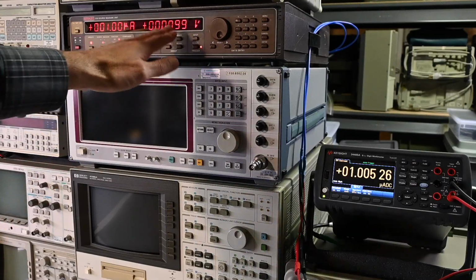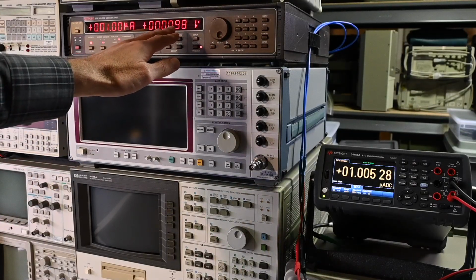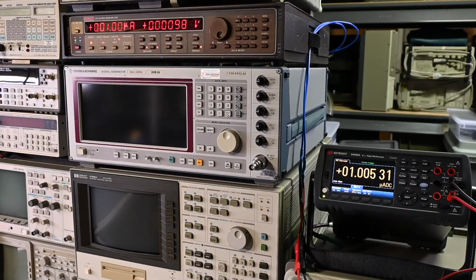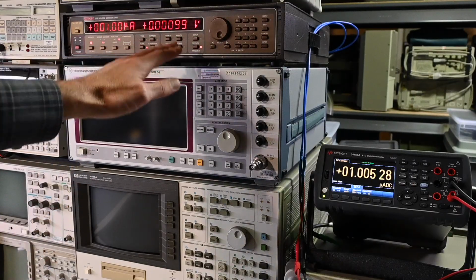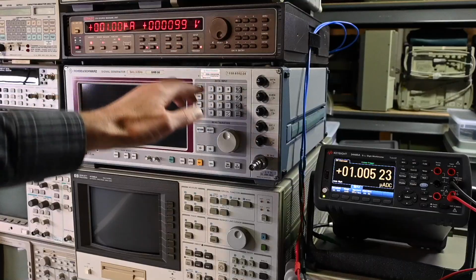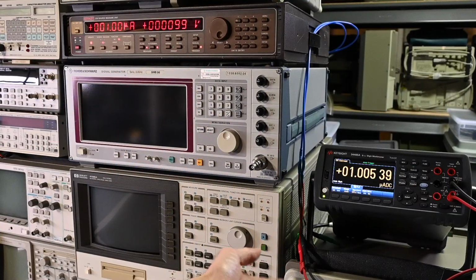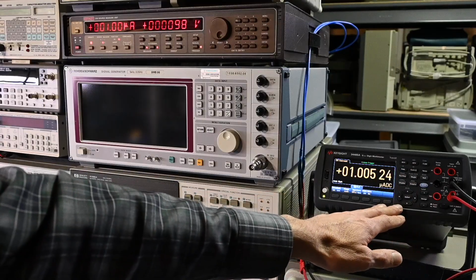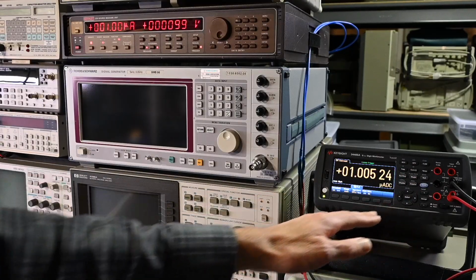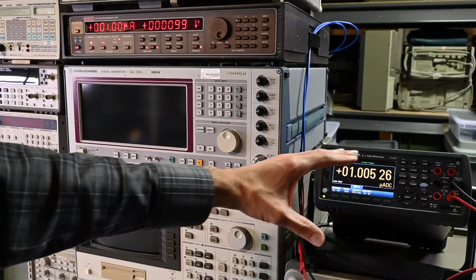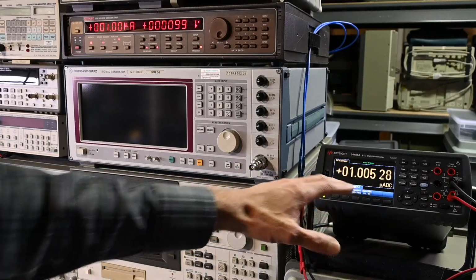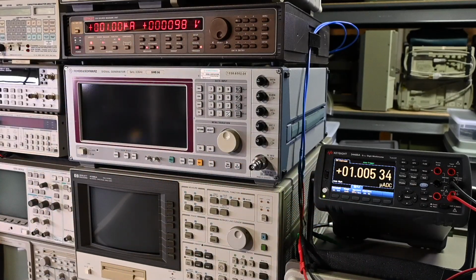Now this voltage measurement is actually the voltage that's being measured at the output terminals of the instrument, because it's not set for remote voltage sensing at this point. I don't have it configured that way. So this voltage is at the back of the instrument, and there's a little bit of resistance in the test leads, not much, but just ever so slight. And then there's some resistance through the current shunt in this digital multimeter, so the voltage drop across the test leads and that current shunt ends up being this voltage right here.